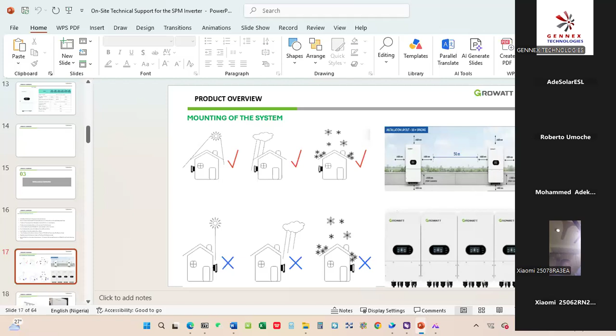You will see it here, as you can see in the illustration. We all agree that when mounting an inverter, it's advisable to use the first picture, because you see that this space allows the inverter to breathe. But when you use the layout in this diagram, the inverter doesn't have space to breathe. So always give space between two or three inverters when connecting them. And like I said, the IP rating is 66, but you are not allowed to mount it directly under the sun, under the rain, or where a storm can hit it. You can have a small shade for it.